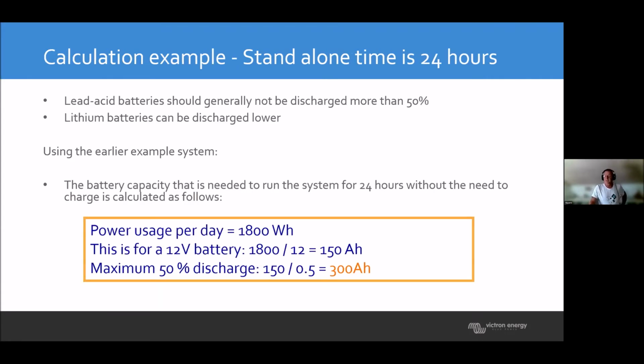Here's a small calculation for a battery bank. The customer is using 1,800 watt hours per day. We're calculating here in 12 volts - if it were a 48 volt system, you could divide that by 4. But in a 12-volt system, this means 150 amp hours.